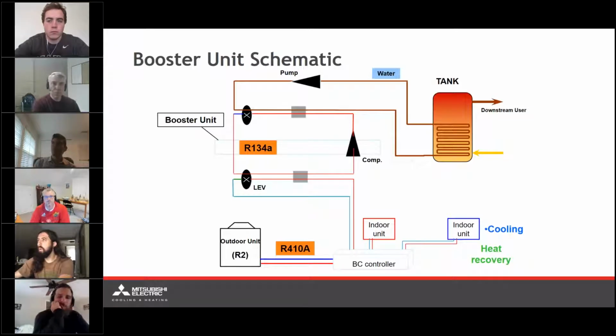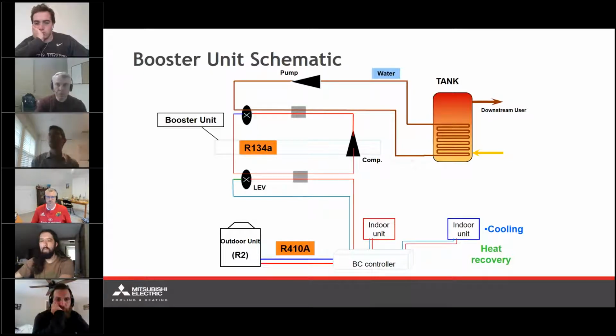All right, so this particular schematic is similar to what we were looking at before, except for this unit, we're going to be utilizing a HEX booster unit in order to boost the water temperatures to hot water temp. It's going to be in hot water mode up to 160 degrees in order to provide preheating to a domestic hot water storage tank.